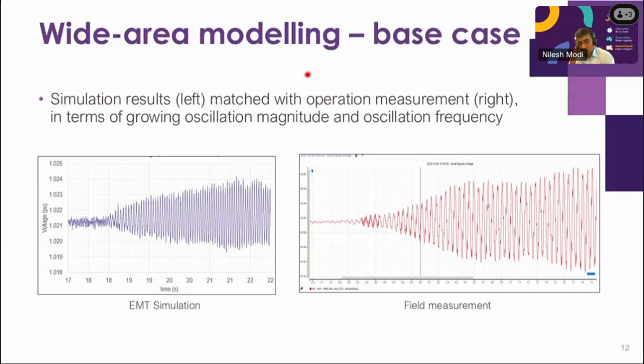So going a little bit further on looking at the wide area modeling. The one on the left hand side is the response of only one bus; I have shown here the voltage measurement at one bus. In the simulation, you can see how it is gradually growing. And on the right hand side, you can see the field measurement, and the fingerprints are aligning, right? So a similar observation, which we noticed through real time measurement, can be replicated in the EMT model, particularly when we change the irradiance at only one IBR.